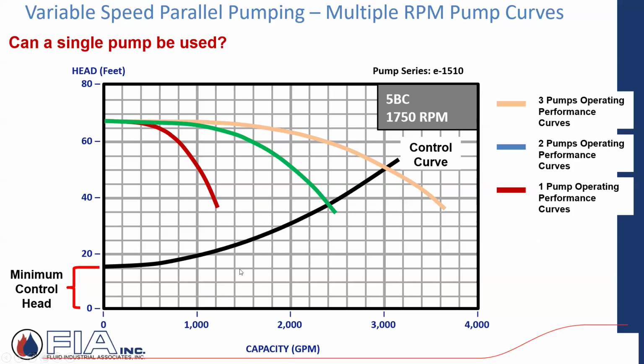This was just a quick example of variable speed pumping with parallel. So multiple pumps in parallel. In this case, it's 3. And they're saying, hey, design conditions are such that I'm looking for 3,000 gallons a minute at 50 feet of head. So 3,000 GPM, 50 feet of head, and I've got 3 pumps in parallel to get there. And so they're showing 3 different curves. They've got this kind of tan or cream colored. I apologize, but this blue is supposed to represent the green, and then the red is the red curve here.